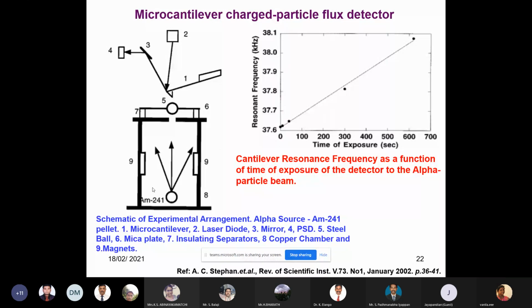They plotted a graph of time of exposure with respect to resonance frequency change. The cantilever was vibrated with a piezo exciter. Because of the alpha particle radiation, the cantilever deflects. Likewise, they are getting a very linear measurement with different exposure times. This confirms that a cantilever can be used very easily for alpha particle flux measurement.